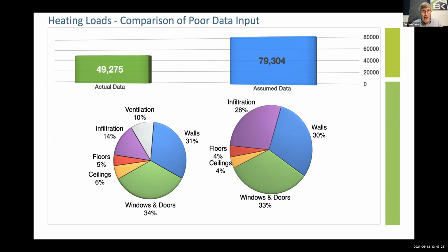This isn't anything to do with the amount of insulation that's put in the house. This is just an HVAC designer not putting in the right numbers. And I know nobody on this call would do this, but I'm just showing you the implications it has. It's not quite twice the size, but it's certainly 2 furnace sizes up. Instead of a 50,000, you're putting in an 80.